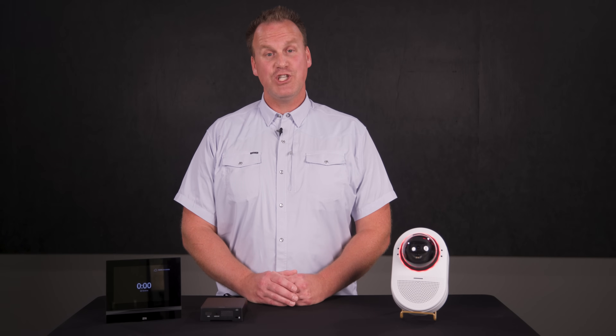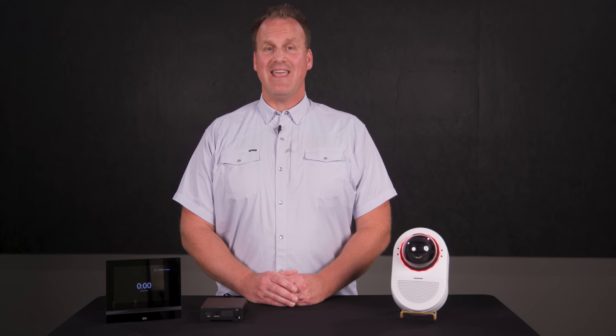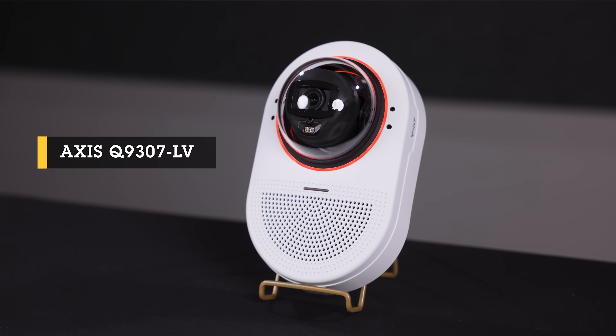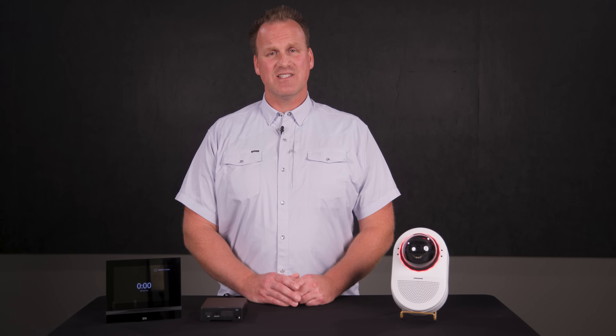However, because these machines use powerful magnets, anything entering the MRI room must be certified and labeled appropriately. The Axis Q9307-LV has been certified as MRI conditional, meaning that this device is approved for use inside of MRI suites.